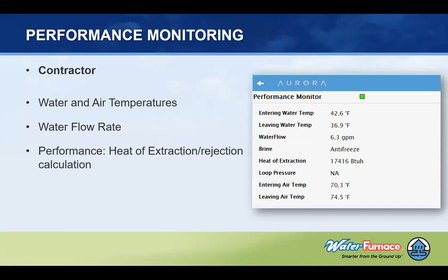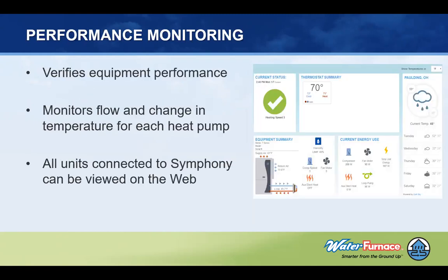The final section of the monitoring kits is performance monitoring, and that's also for the contractor. It gives you water and air temperatures and the flow rate, and that allows you to know the exact performance. So as you saw, the consumer gets to know what their loop temperature is and entering and leaving air. They don't see the exact performance and the BTUs from the system. This actually verifies the equipment performance and it gives you, for any of the systems that are connected to Symphony, the performance on a multi-home system or multi-unit home.